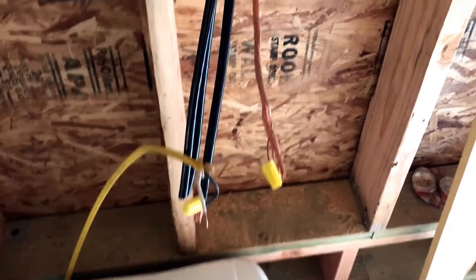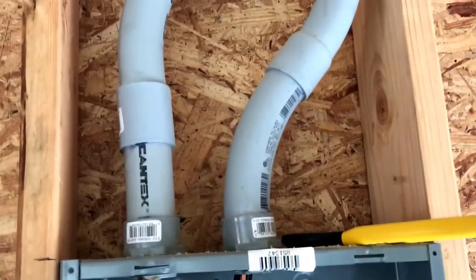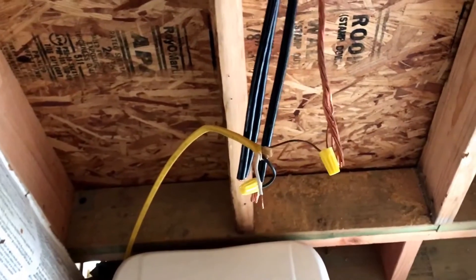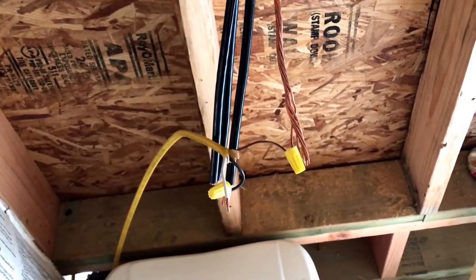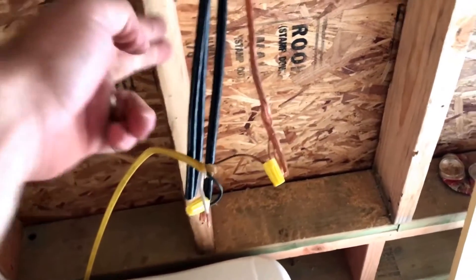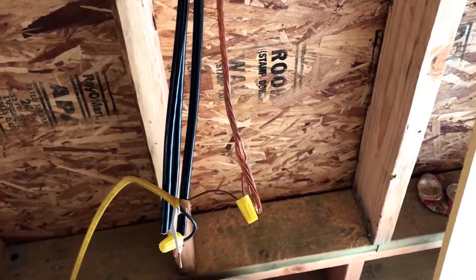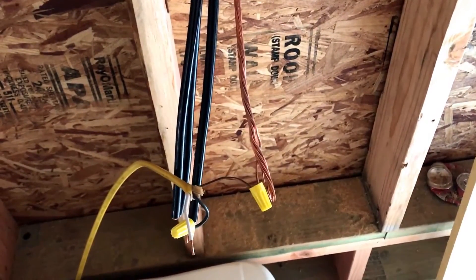I made a really silly mistake when I was pulling these main power wires through the conduits. I laid out all three wires all excited, taped the ends together real quick, fished them through the conduit, and then realized I forgot to mark one of them to be my neutral. So two of them will be the primary hot lines, and then one is your neutral, which can only be white, but it's all the same-looking cable. I didn't get a white cable.